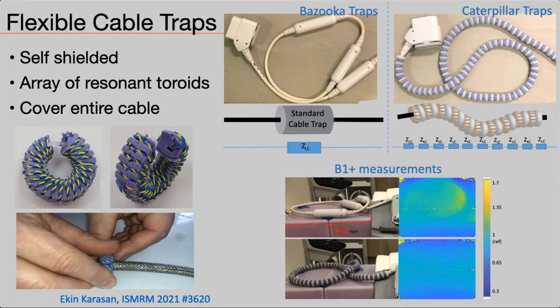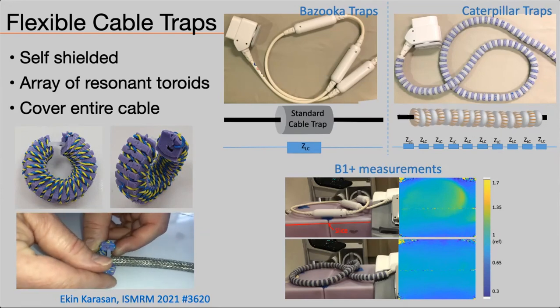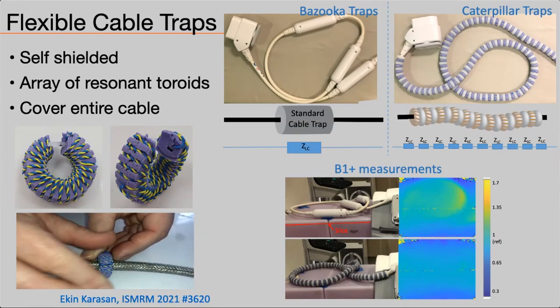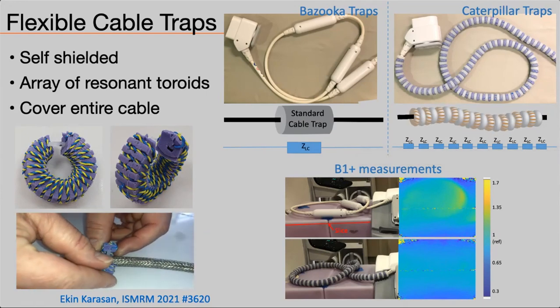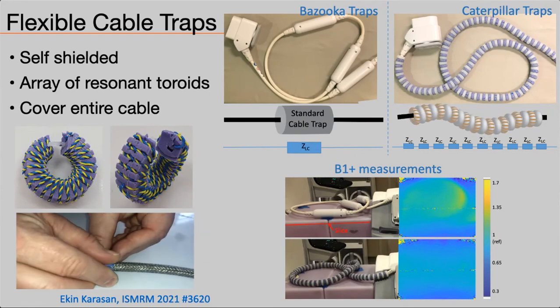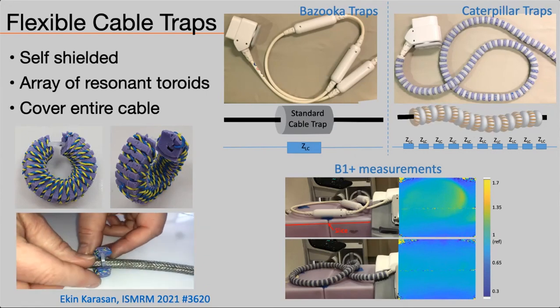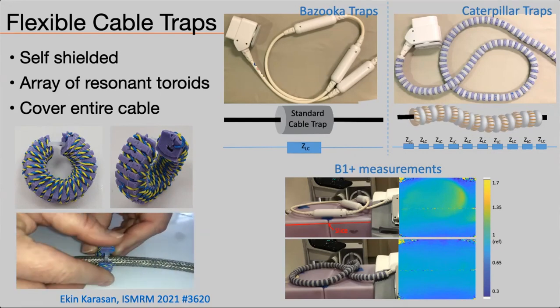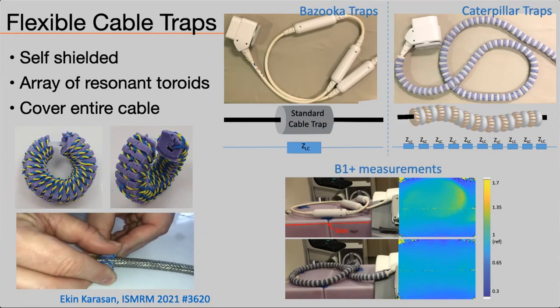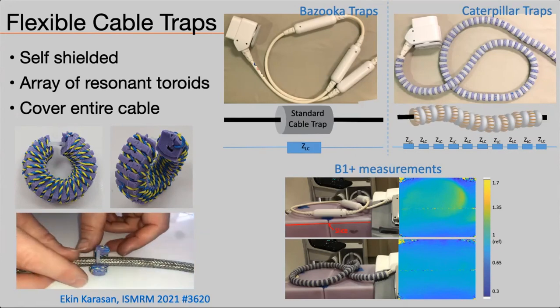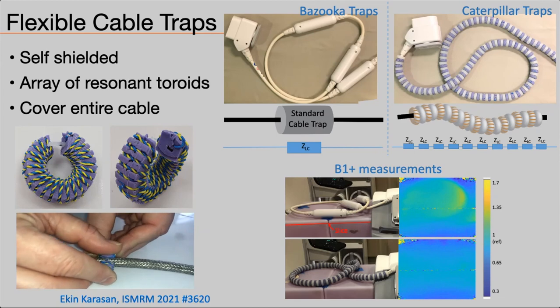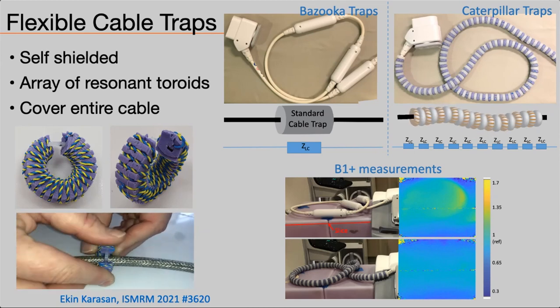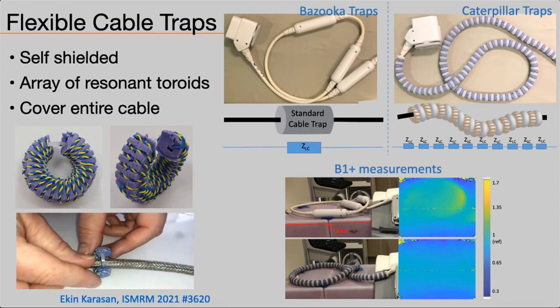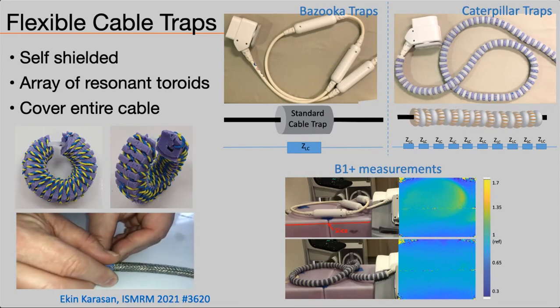It's like the B1 measurement, where you have a target flip angle you're targeting, and in this case it's 30 degrees. So it's basically whatever the measured flip angle is over the target flip angle, for both cases. So it's off by 30% or so, maybe even a bit more in the top case. If it was 30 degrees, it's about 10 degrees off, so it's going to be 20 to 40, maybe 40-45 degrees.